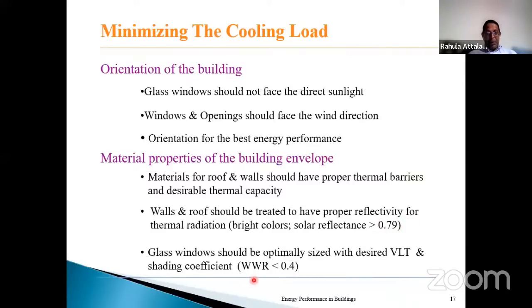And WWR is the window to wall ratio. Windows should not be very large. Window area divided by the wall area should be less than 40%. So that's why. These are two important elements that are given in the standards.